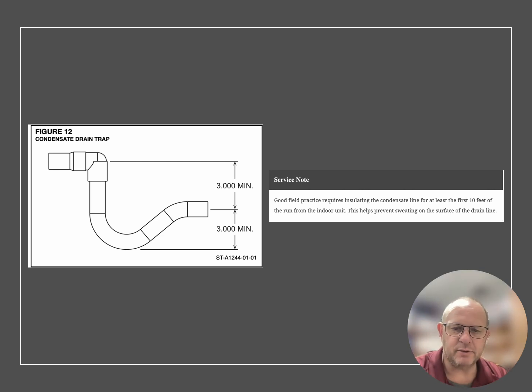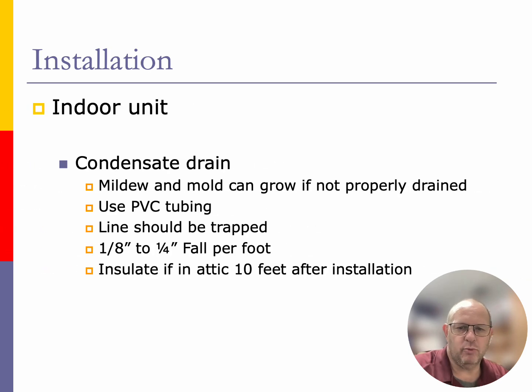Another reason that we want to run that condensate line is we want to pitch it in such a way that we don't start to develop any mold or mildew growing on that particular drain pan. That can be detrimental to our customers, but also it can smell so that they would smell a foul smell whenever the air conditioner kicked on, and that's not what we want. We want to use PVC piping, which is non-corrosive, so we're not going to deal with ferrous metal piping, no black iron, no galvanized on our indoor units. Try to stick with PVC piping.